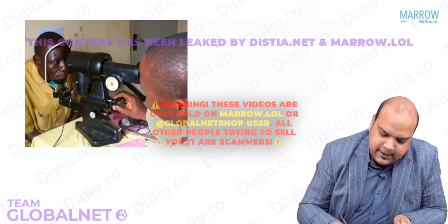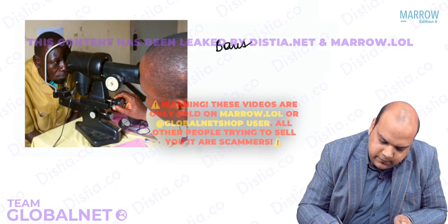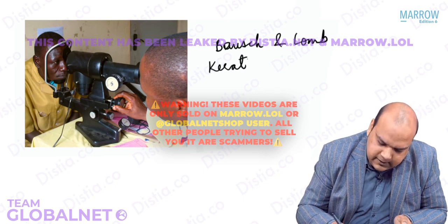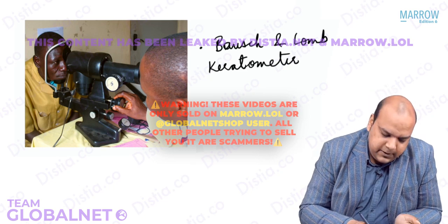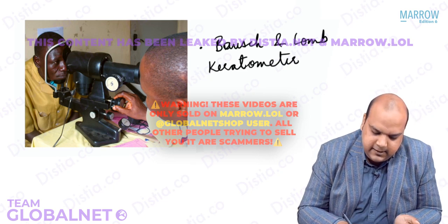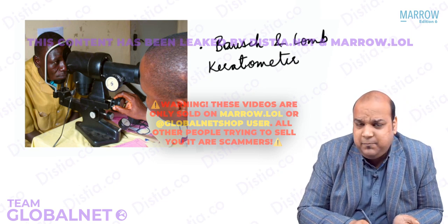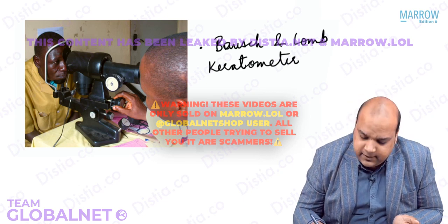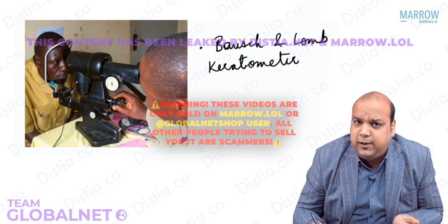The instrument which we use is this instrument. This is called Bausch & Lomb. Bausch & Lomb is obviously the company, guys. So Bausch & Lomb keratometer, B&L keratometer. This is a manual keratometer. Obviously, as you will be able to make out, the patient will keep his or her face here. The examiner will be visualizing by throwing some light on the cornea of the patient. Now, when the examiner is visualizing, what is he or she visualizing? When the light is thrown from the keratometer onto the patient's cornea, this is what we are able to see.